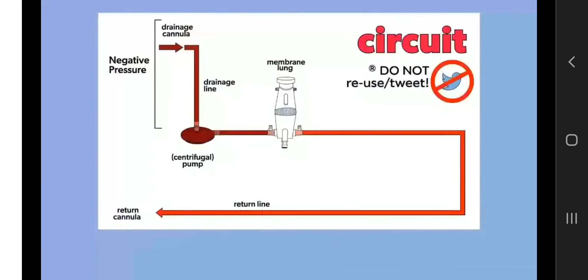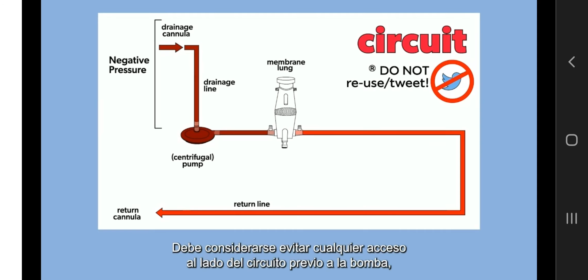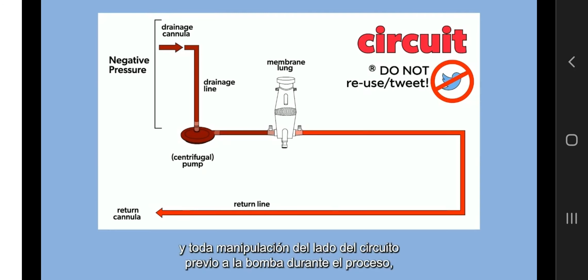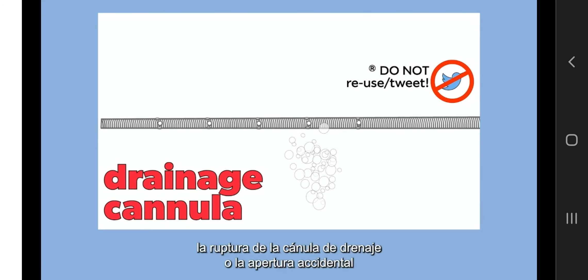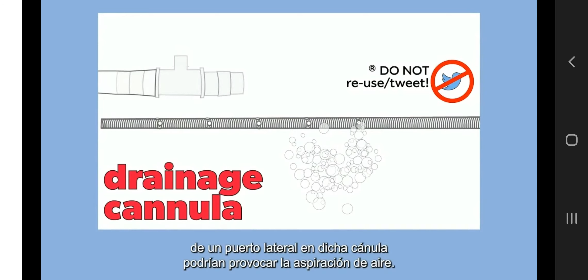During the run, any breakage, disconnection, or opening of connectors within the pre-pump side of the circuit, which is the negative pressure side from drainage cannula to the center of the pump head, will induce aspiration of atmospheric air. Consider avoiding any access on the pre-pump side of the circuit, including connectors with side ports, and avoiding any manipulation of the pre-pump side of the circuit during the run, if feasible. For the same reason, misplacement, displacement, or even partial displacement or rupture of the drainage cannula, or accidental opening of a side port on the drainage cannula, could induce air aspiration. Again, consider avoiding the use of connectors with side ports on drainage cannulae.